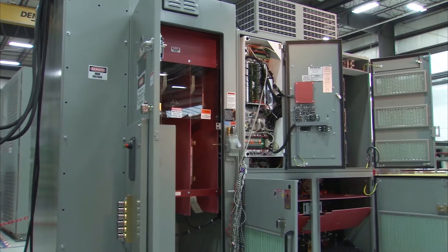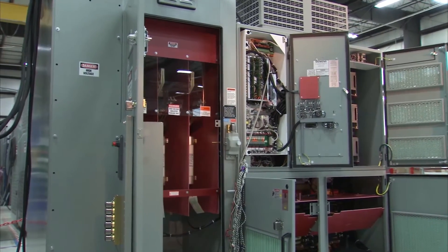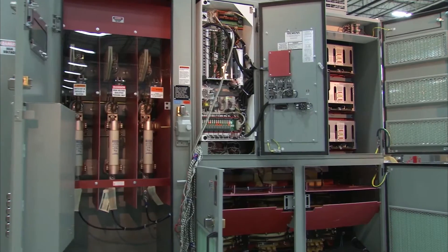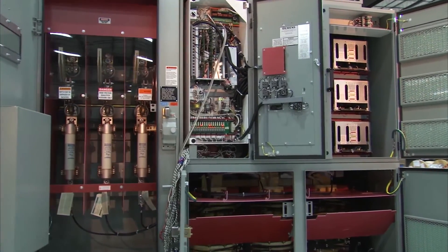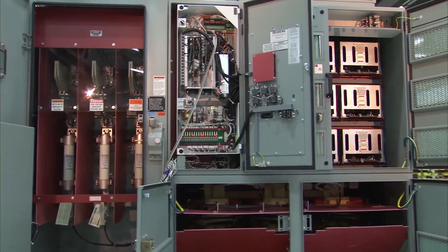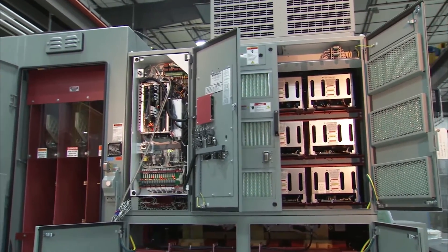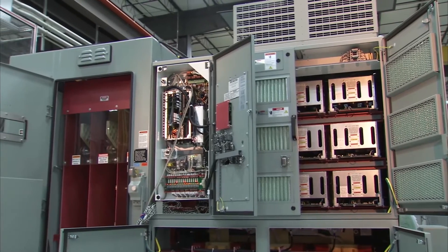Siemens Sinamics Perfect Harmony GH180 air-cooled drives are engineered for top performance. That's why it's fast and easy to replace a failed cell. Just follow a few simple steps and you'll be back up and running quickly. We'll show you how once medium voltage power has been removed and the K1 key is extracted from the medium voltage switchgear.